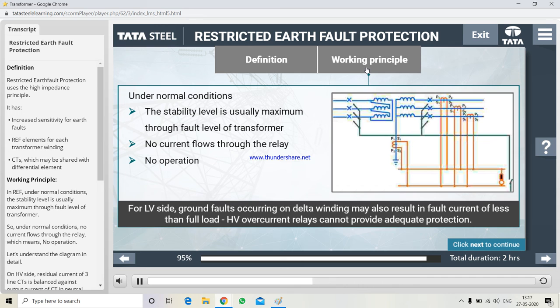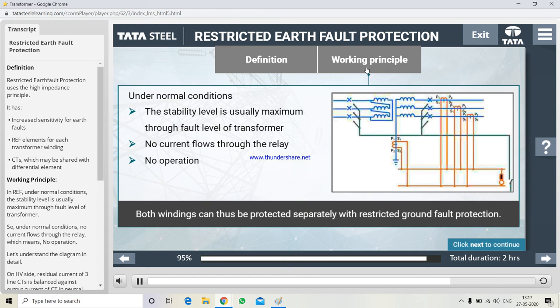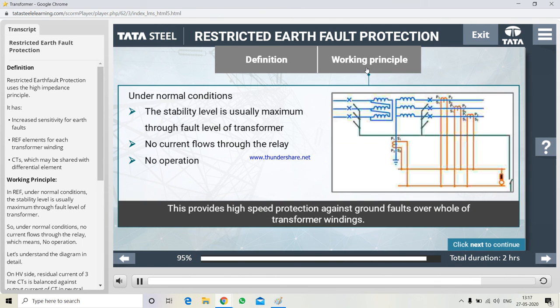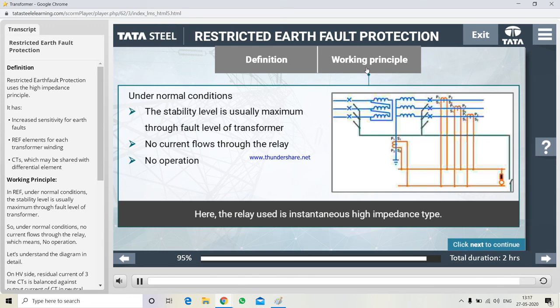For the LV side, ground faults occurring on the delta winding may also result in fault current of less than full load. HV overcurrent relays cannot provide adequate protection. A relay connected to monitor residual current will provide restricted ground fault protection, since the delta winding cannot supply zero sequence current to the system. Both windings can thus be protected separately with restricted ground fault protection. This provides high-speed protection against ground faults over the whole of the transformer windings. Here, the relay used is the instantaneous high impedance type.